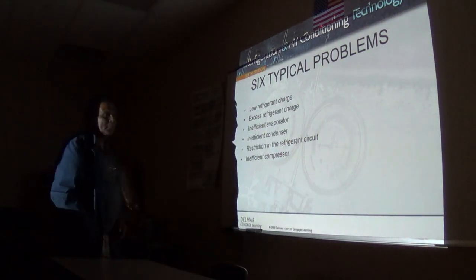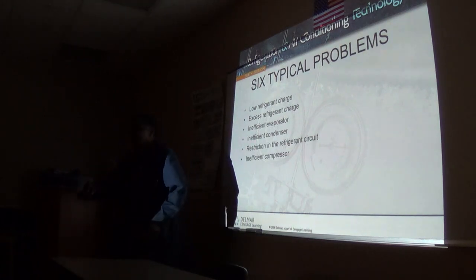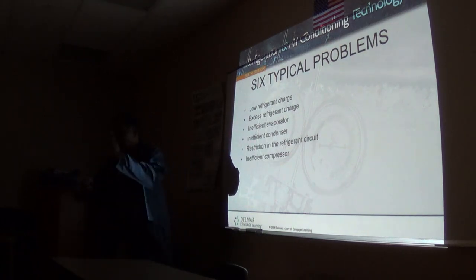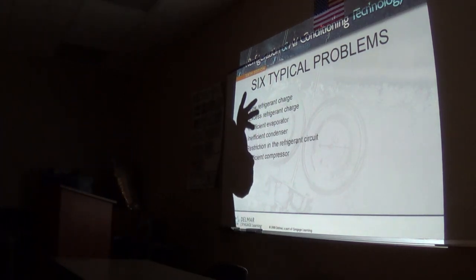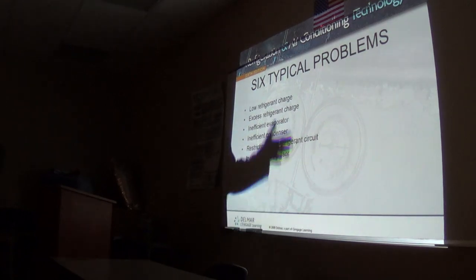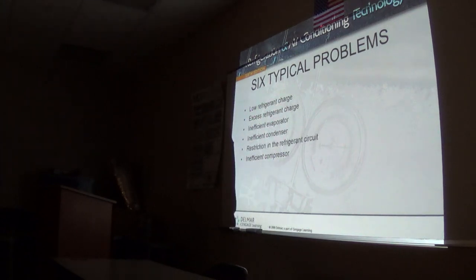Can't you make an adjustment on the TXV though? Can you adjust that metering device? You can adjust it. We do not advise that. We don't even teach you to touch it. It's factory set, right? And once you change that setting, you have to wait like 15, 20 minutes for every quarter turn.